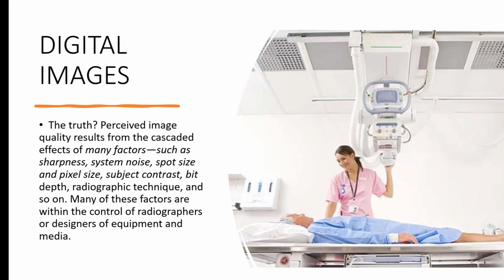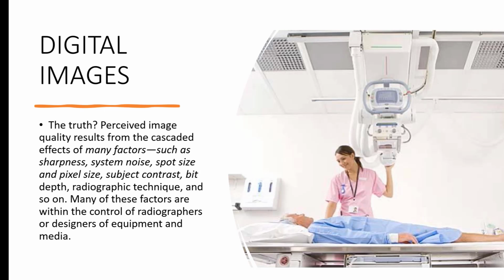The truth? Perceived image quality results from a cascade of effects and many, many factors, such as the sharpness, the system noise, the spot size, the pixel size, the subject's contrast, the bit depth. Bit stands for binary digit, and if I had 8-bit depth, it's 2 to the 8th, which would give me 256 shades of gray, whereas if I have 10, I have 2 to the 10th, which would give me 1024 shades of gray to choose from.